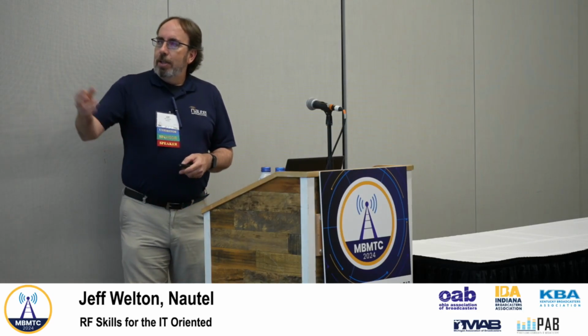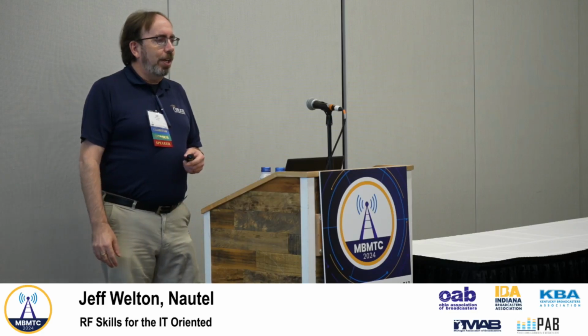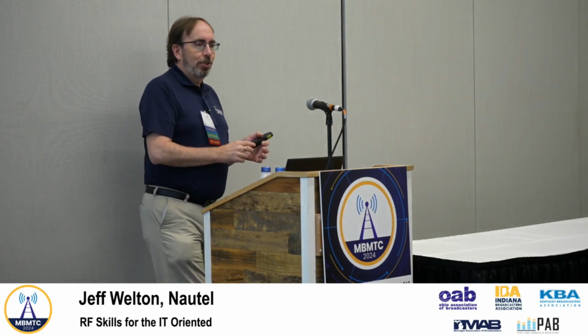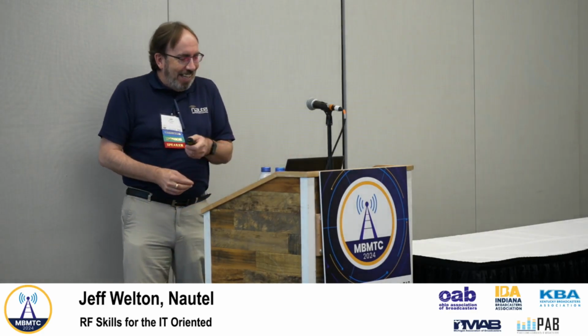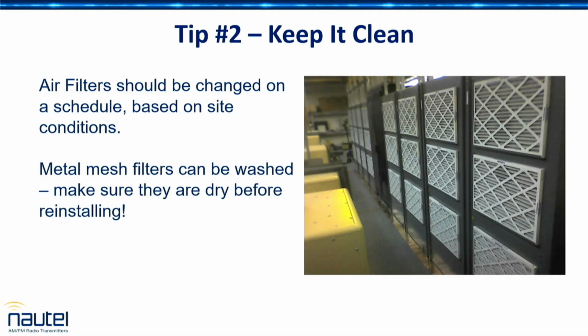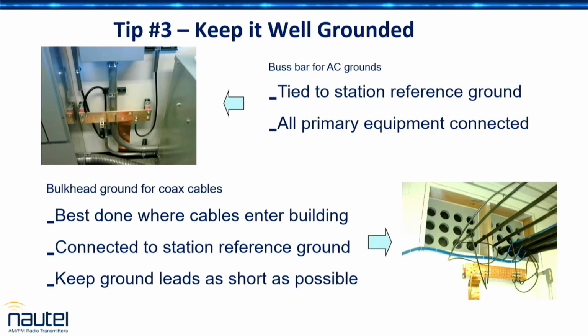If you're running forced air, check the air filters on occasion. I didn't put your picture up on this one - so I did a tour through Minnesota, Wisconsin, and Michigan one June, and I stopped at a bunch of sites, taking a picture from each state showing an air filter totally clogged solid with cottonwood fiber. One of them happened to be one of his, and he'd just cleaned it a couple of weeks earlier. Like I tell people, the maintenance schedule you use will be totally decided by the condition of the site and the environment - it's nothing I can tell you. I'll tell you how often to tighten the hardware, though.